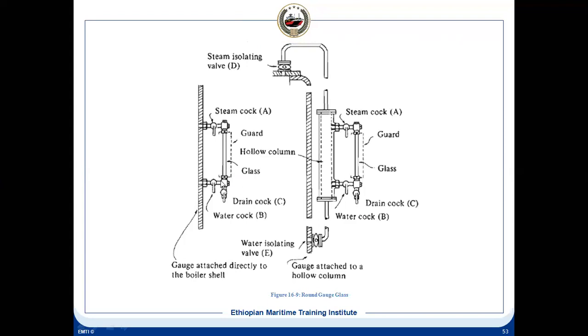In this type of design, you usually have a small metal ball fitted inside. As long as the gauge glass is fine, the metal ball basically does not block any of the passages.